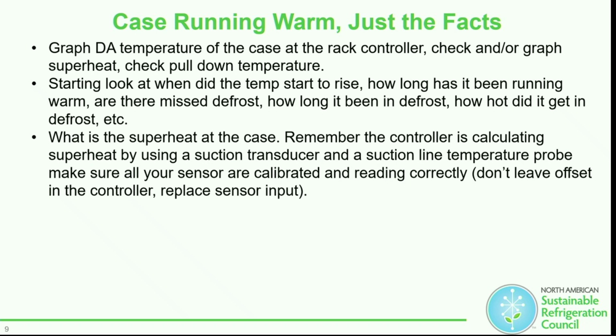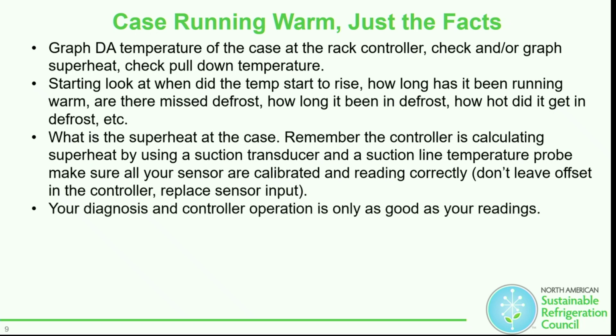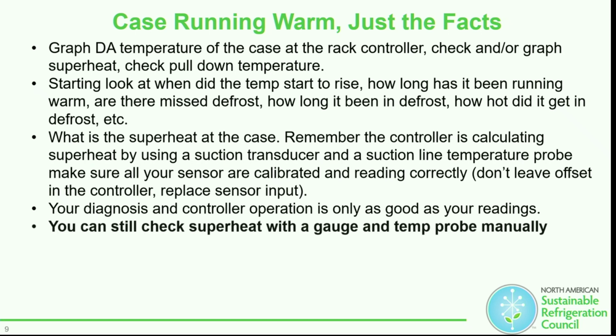Also make sure all your sensors are calibrated and reading correctly. Don't leave an offset in the controller. This isn't a Friday call, so we can't just put an offset and bounce. Your diagnosis and your controller operation is only as good as your readings, so everything has to be working. If the controller is supposed to be operating at an 8-degree superheat and it's getting lied to by the numbers, where it's not actually calculating the right superheat, you're not going to have proper operation of that system. You can still check the superheat with a gauge and a temperature probe manually.